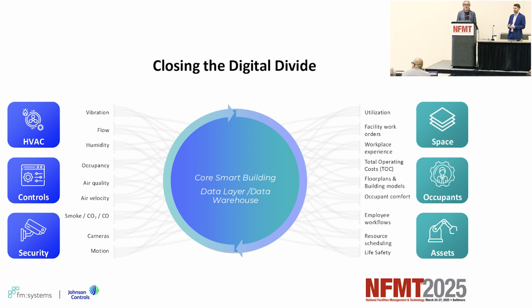The next layer is that when we bring that data into a central location, we want to make sure any vendor has a plan to structure that data. You may hear terms like haystack, brick, and data models. It's not just about pulling data from local systems and knowing this is a return air temperature point or a damper position at a given moment—it's the relationship of those systems.